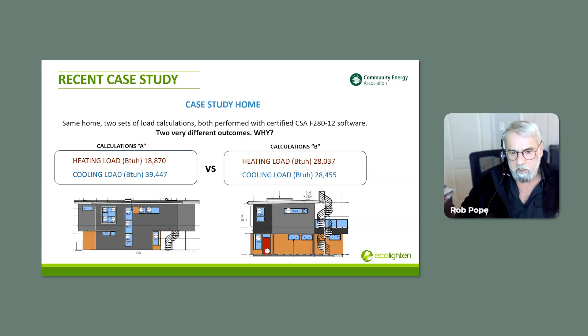That HVAC contractor didn't realize we had done load calculations - he thought it was just a guideline. So he sent it to a third party and got his own load calculations done. Look at the difference: same house, two different load calculations. Our calculations, calculation A, were 18,000, almost 19,000 BTUs heating load; theirs went up to 28,000 BTUs. Our cooling load was shockingly 39,000 and change; their cooling load was 28,000. Obviously this is an issue we have to figure out.